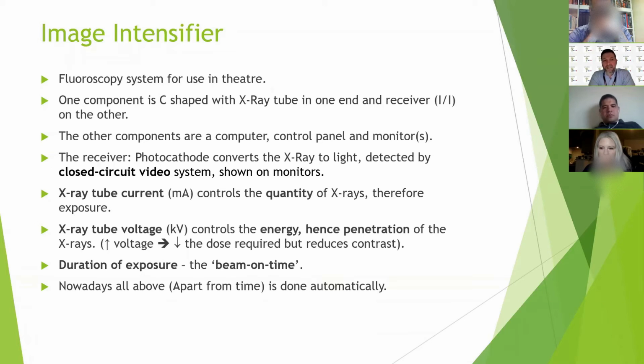So now you've defined it, you describe how it is done. It is like your X-ray. There is a photocathode converter that converts the X-ray on the receiver to light, which is then detected by a closed circuit video system and shown on the monitor. You should also be able to describe how X-rays are made: a vacuum tube, tungsten, electricity, high velocity, and then hitting a tungsten plate. But for the image intensifier itself, this would be enough.